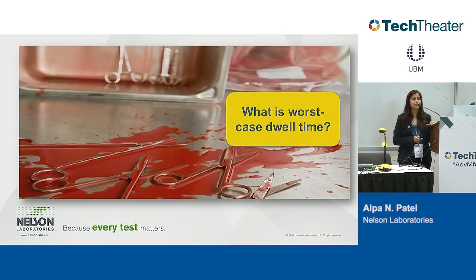When we talk about worst case dwell times, we're also mimicking that in the validation. We're trying to simulate the time it takes between procedure and reprocessing. What I mean by that is when you go to the healthcare facility, it is not reprocessed right away. It takes time to go to the central processing unit where it's going to be processed, and then from there, it gets cleaned. It could be 8 hours, it could be 4 hours, it could be 72 hours before your device gets reprocessed. And that's what we're mimicking at this point.